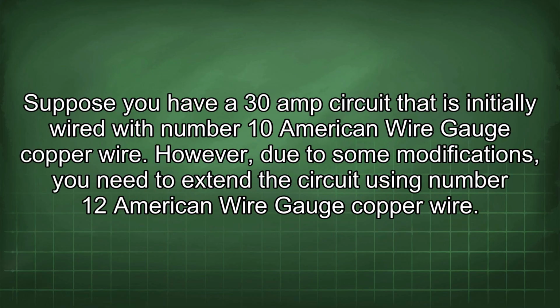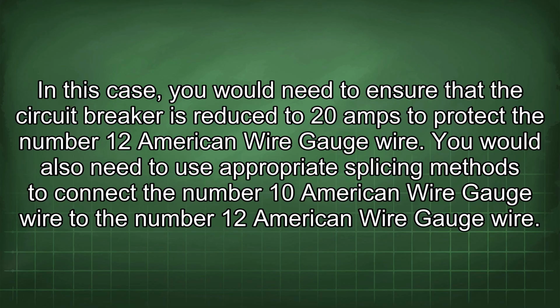Suppose you have a 30 amp circuit that is initially wired with number 10 American wire gauge copper wire. However, due to some modifications, you need to extend the circuit using number 12 American wire gauge copper wire. In this case, you would need to ensure that the circuit breaker is reduced to 20 amps to protect the number 12 American wire gauge wire. You would also need to use appropriate splicing methods to connect the number 10 American wire gauge wire to the number 12 American wire gauge wire.